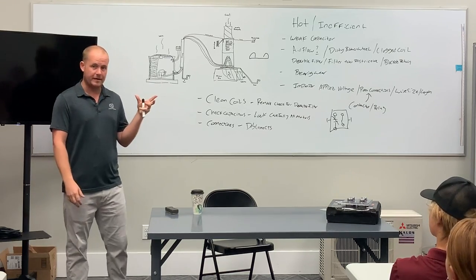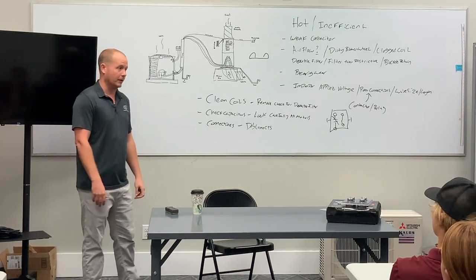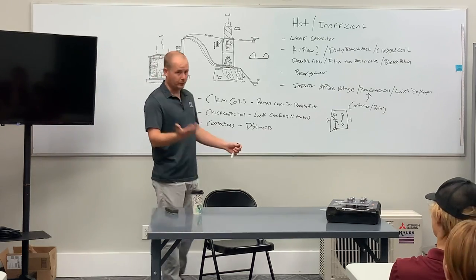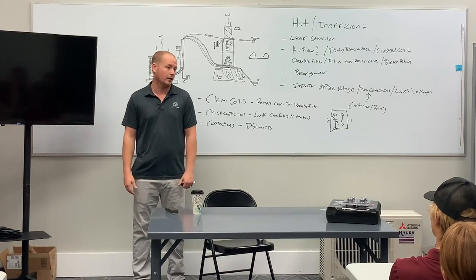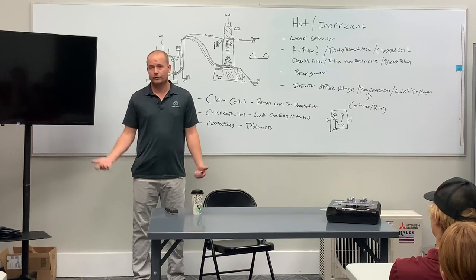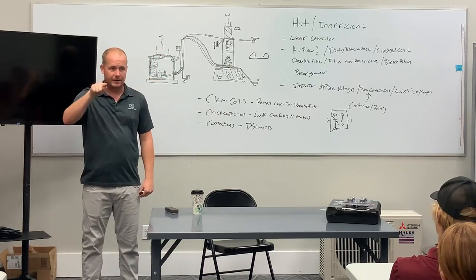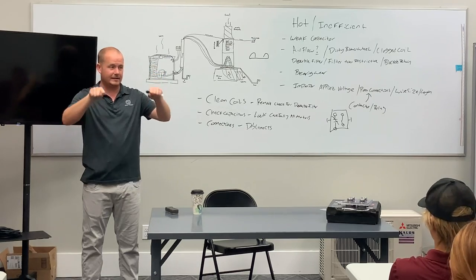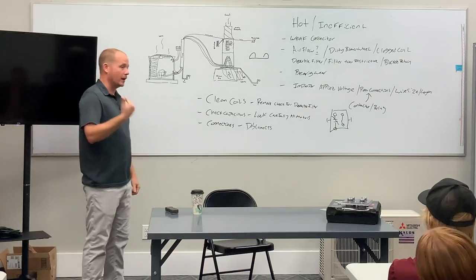So a disconnect should be firmly fastened using the proper screw for whatever the substrate is. If it's concrete or stucco or whatever, you need to use Tapcons. If it's wood, then use wood screws, right? But then you should also seal the top and down the sides of that disconnect with silicone. We've talked about this a lot. It's not hard at all.